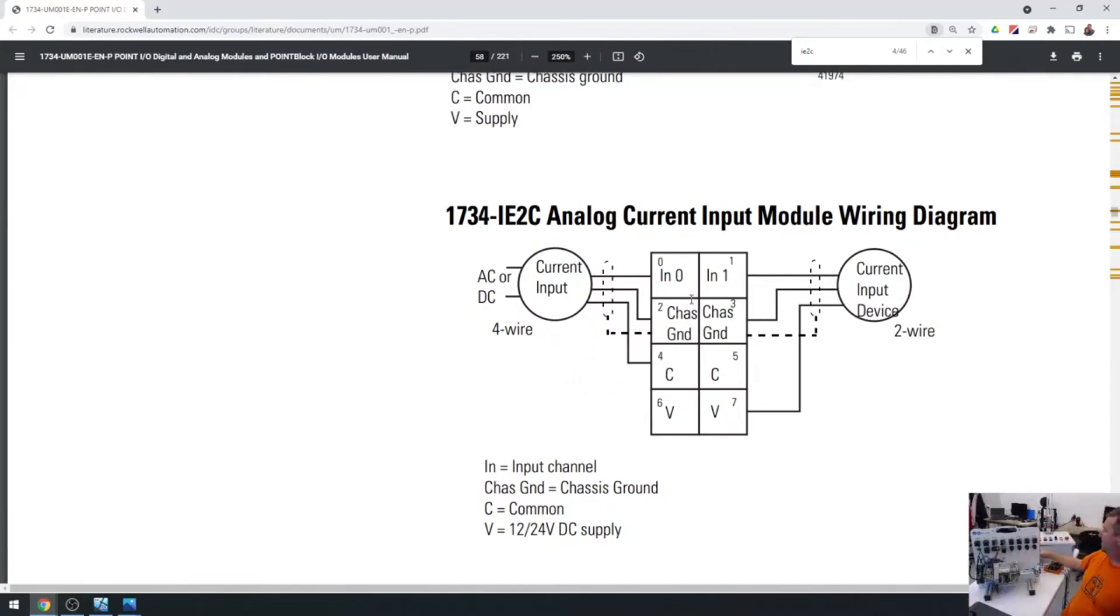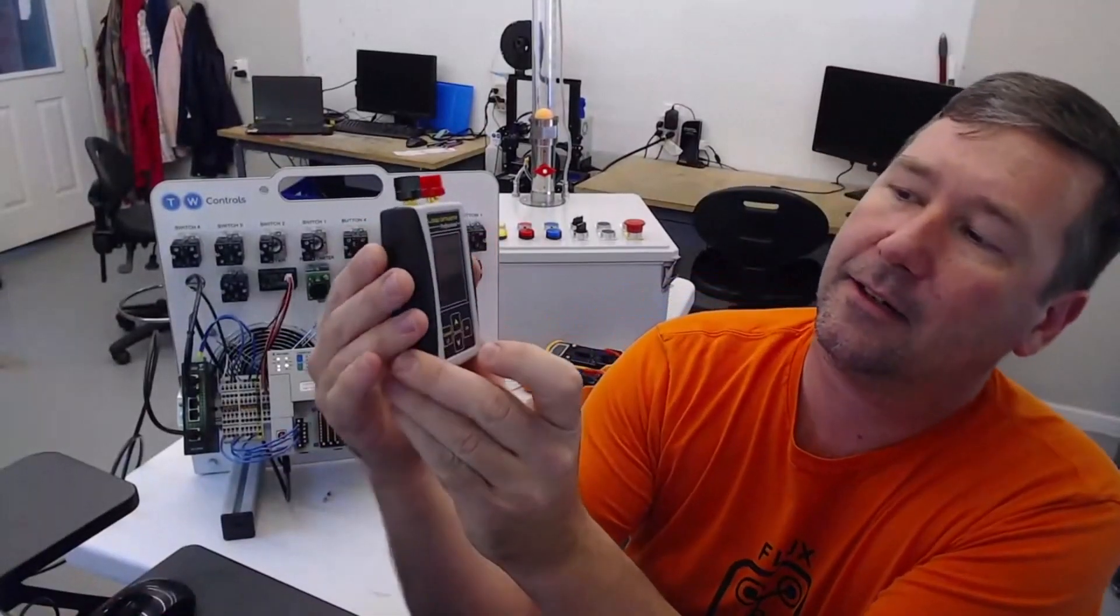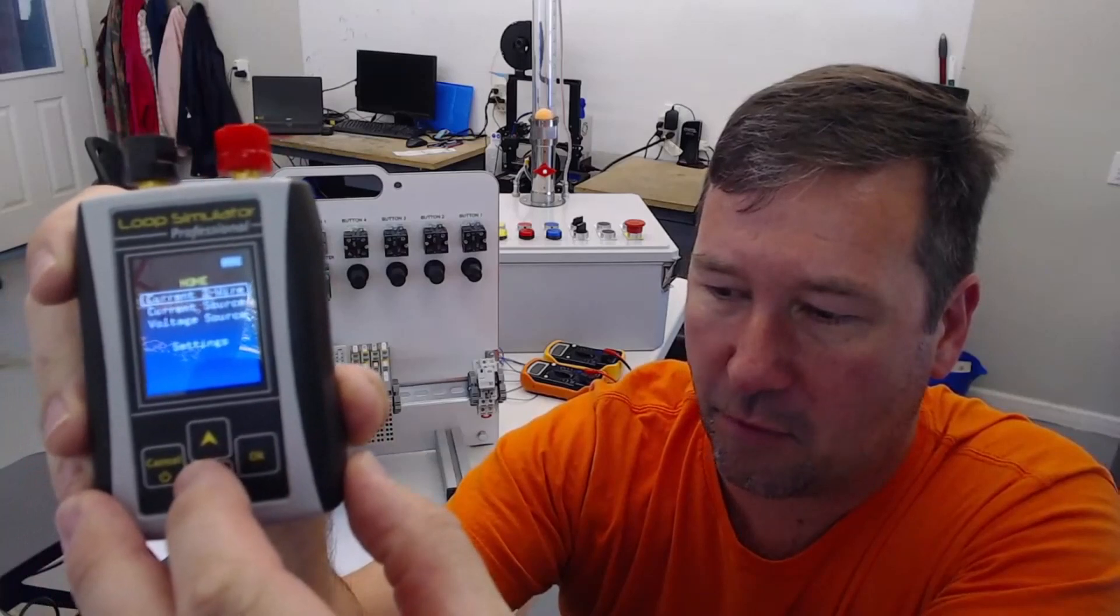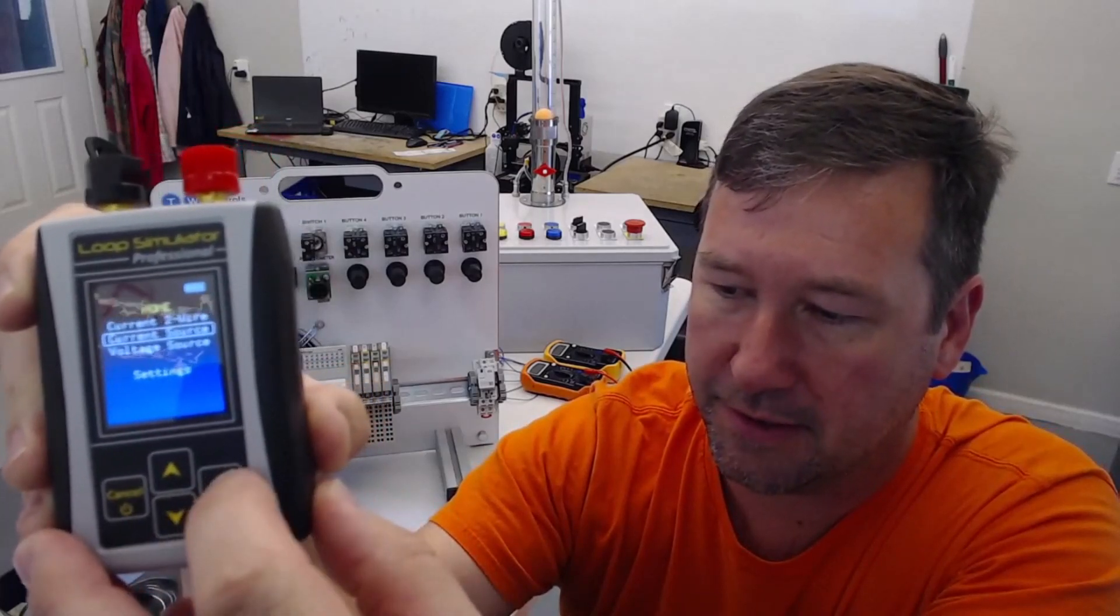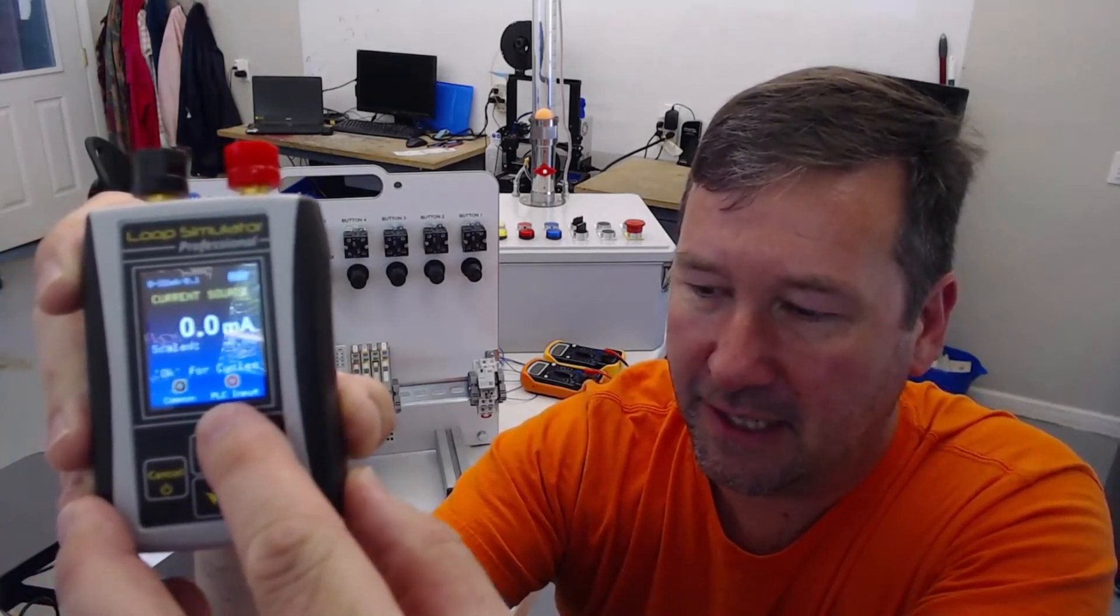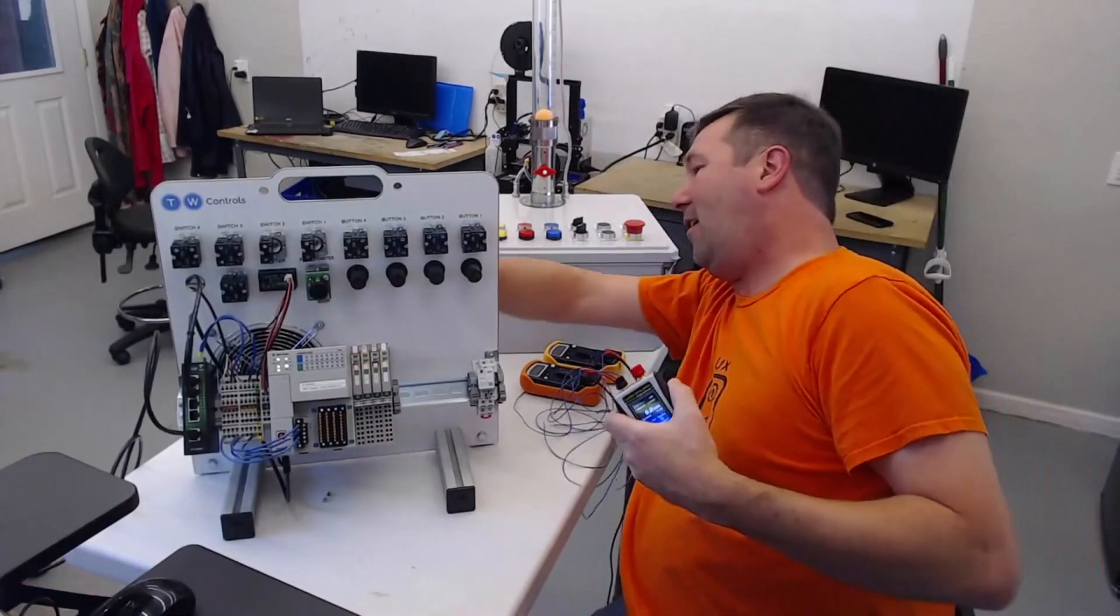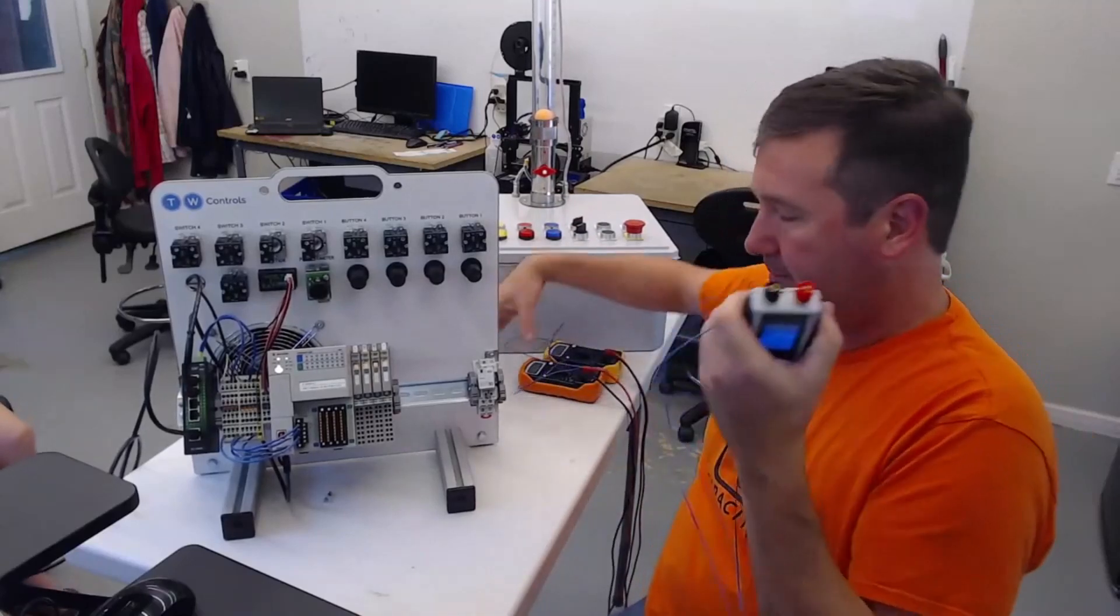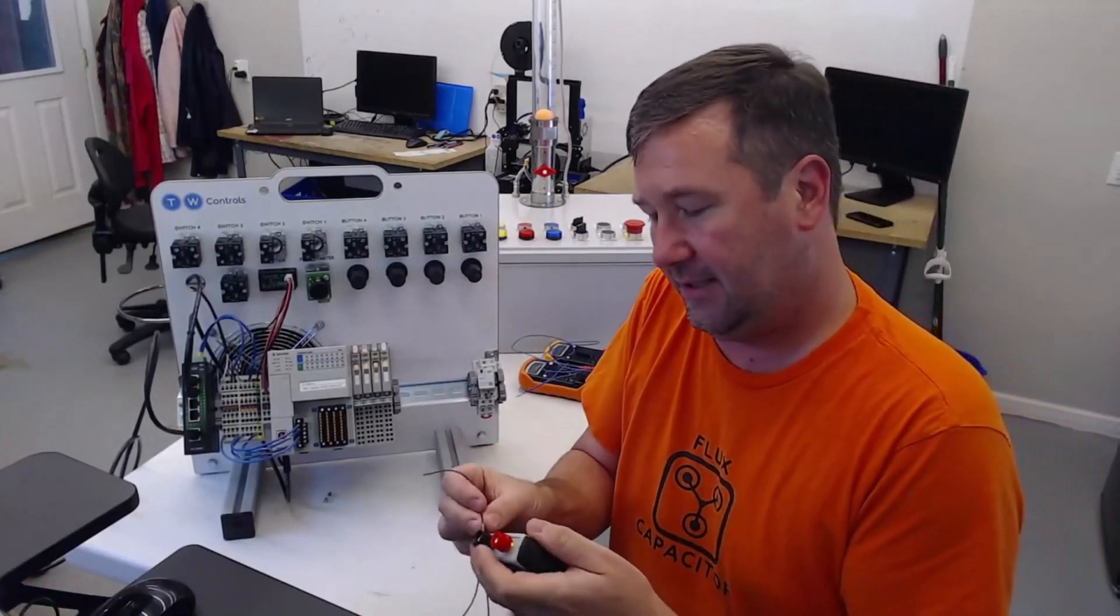We're going to look at our analog simulator. If we go to current source, because a four-wire device is going to be a current source, then at the bottom you're going to see that the red terminals are PLC input and the black terminal is the common. I'm going to turn the power off to the trainer and grab a couple wires and hook them to the analog simulator.